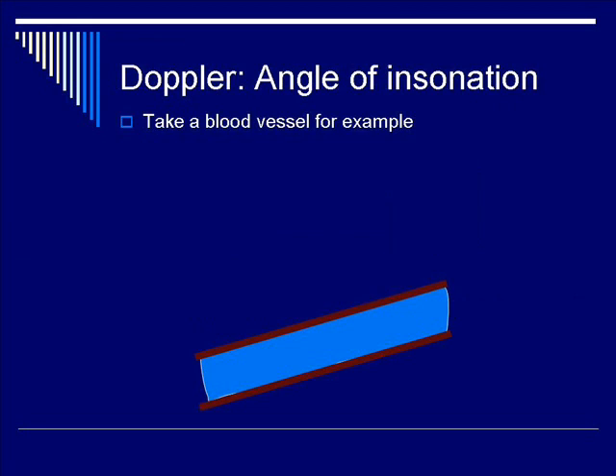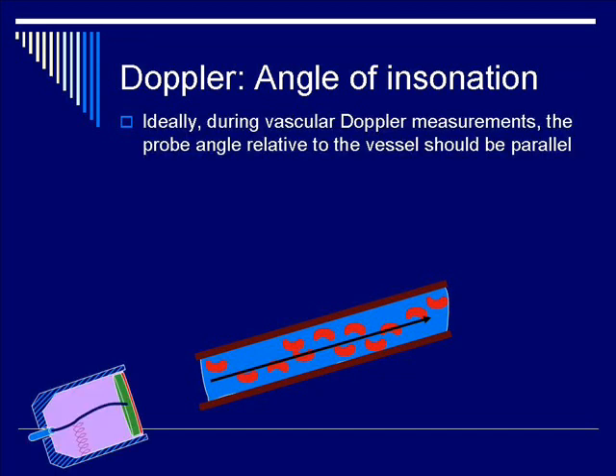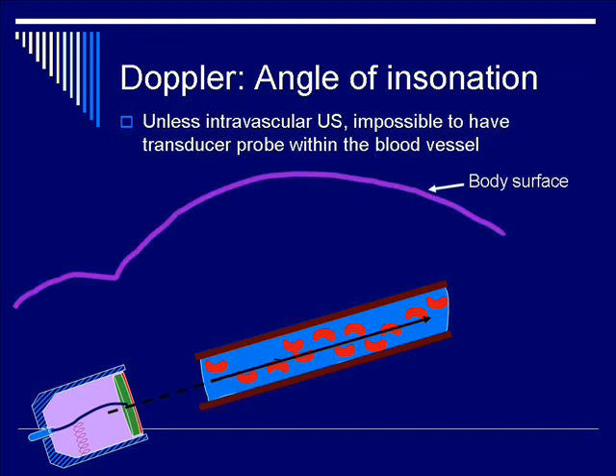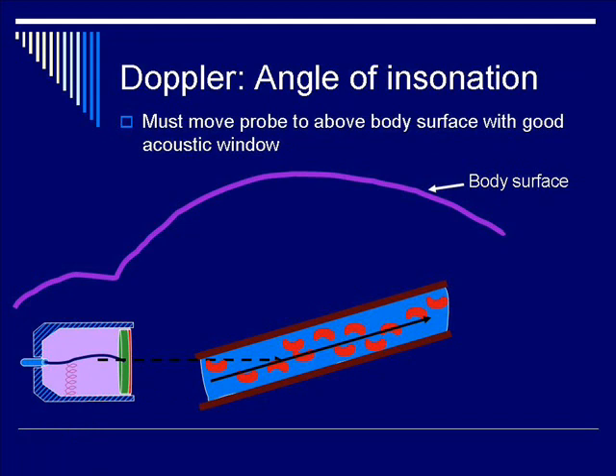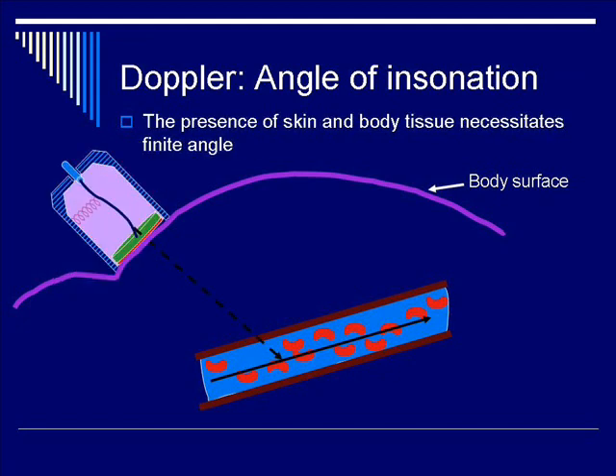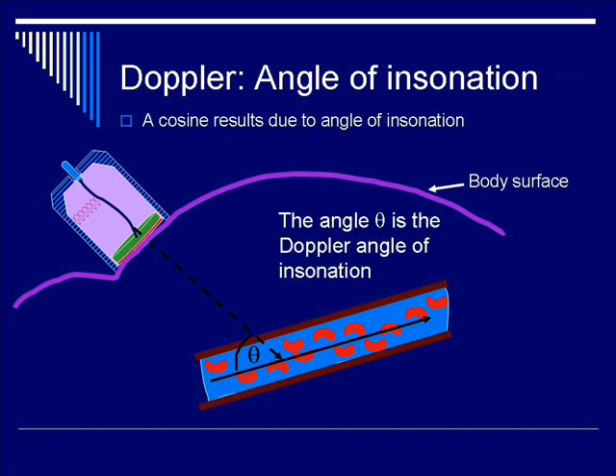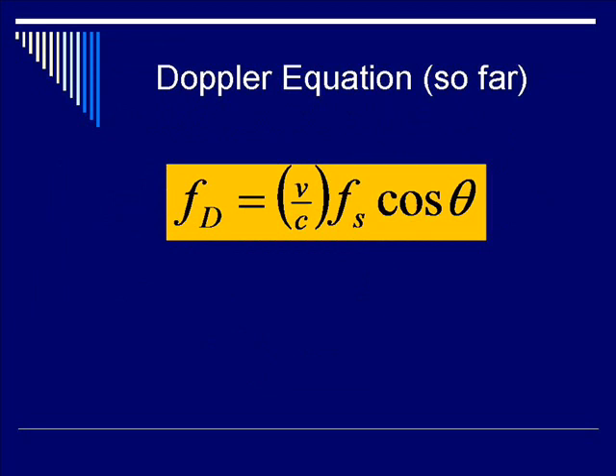The next component to incorporate is the angle of insonation. Ideally, if a transducer faces directly into the vessel at zero degrees, that is ideal — a parallel probe angle. However, in real life you have body surface to contend with. When placing an ultrasound probe on the abdomen to look at abdominal arteries, an angle forms between the line of sight of the probe and the direction of the vessel, called theta — the Doppler angle of insonation — the cosine of which must be incorporated into the Doppler equation.